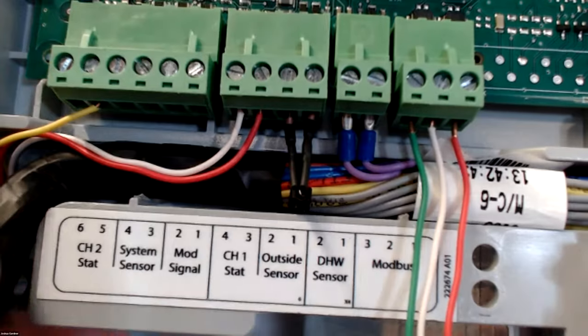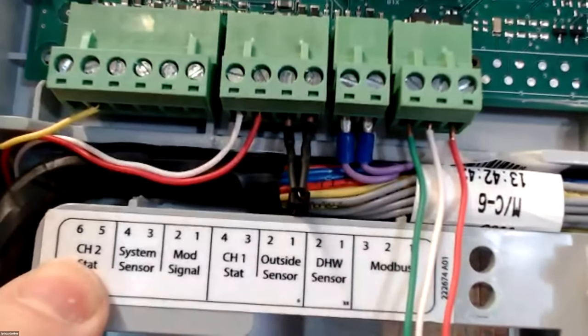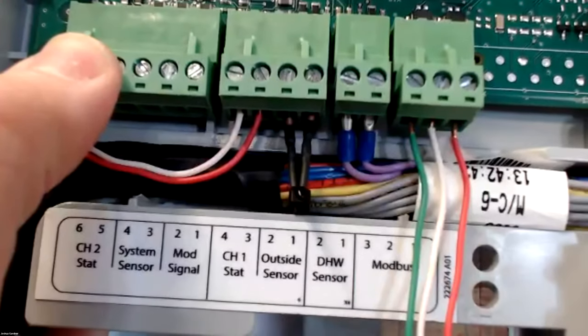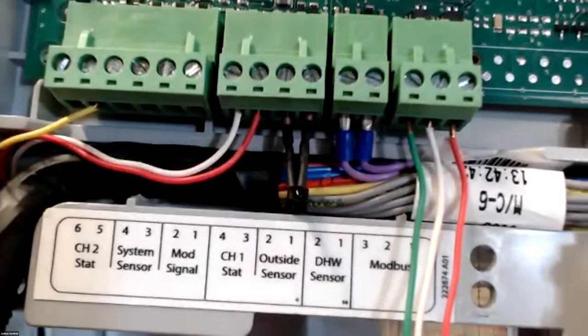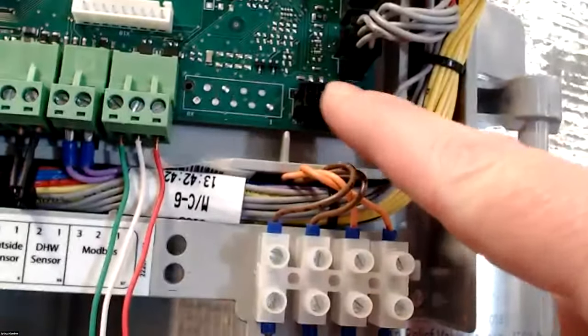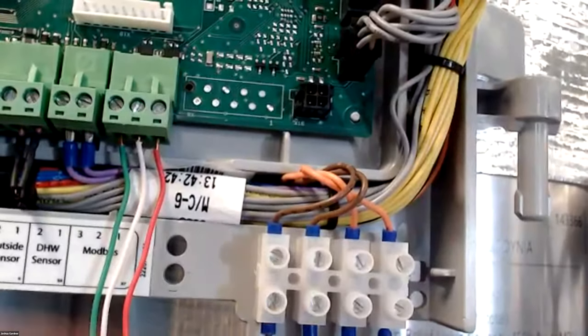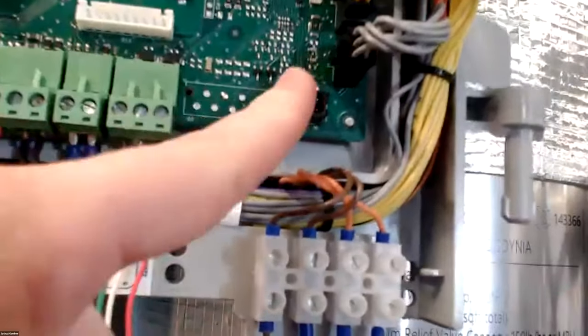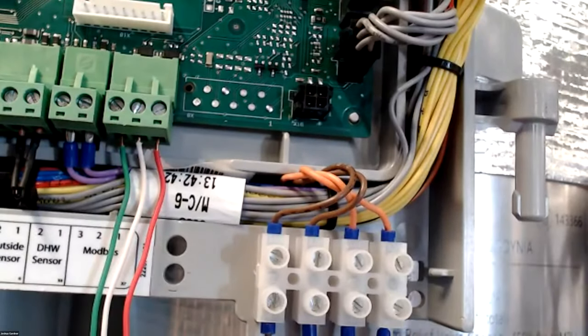Then the last one is CH2. That again is the central heating 2 second zone thermostat, which will be connected right there. Okay. Also in this control panel, we have the connection right here for the cascading cable. So this will go to the next boiler, and the next boiler, but that's where that cascade cable plugs in. Then up top here, just take this off, 3 fuses, 2.5 amp fuses right here. These are for our relay contacts. Then we have our connections for our fan, gas valve, pumps, high voltage up in here. And then all our communication and sensors are on this side.